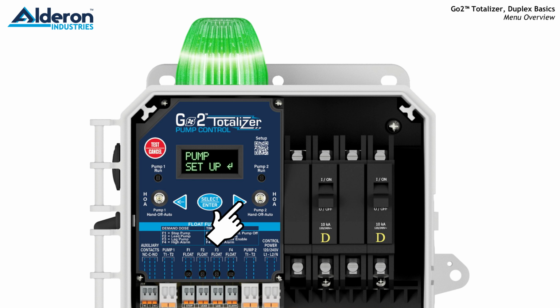If you want to make changes to pump setup, you can change high amp cutout, lead pump, pump 1 configuration, and pump 2 configuration. Under high amp cutout, you can choose either enable or disable. Enable means when in high amp alarm, the pump will be automatically turned off. If disabled, then only the alarm is activated. Under lead pump, you can change from normal alternation, Pump 1 to always lead or pump 2 to always lead.